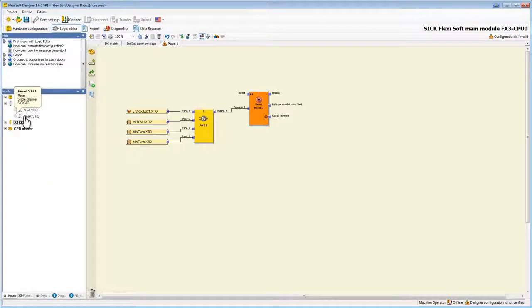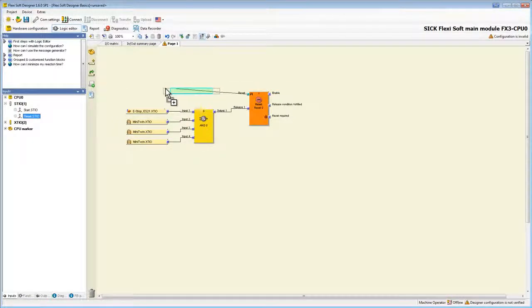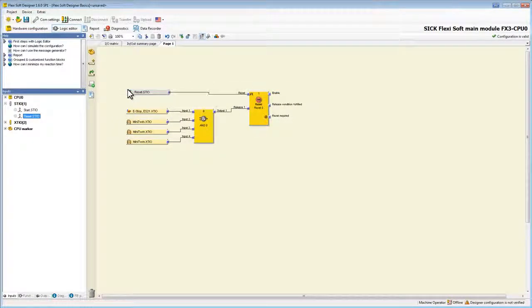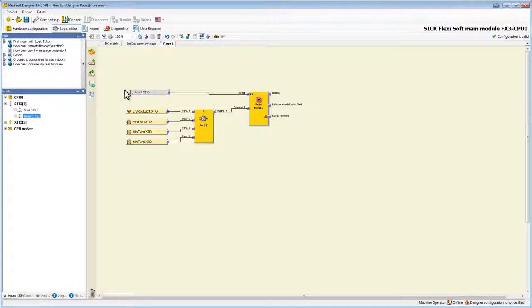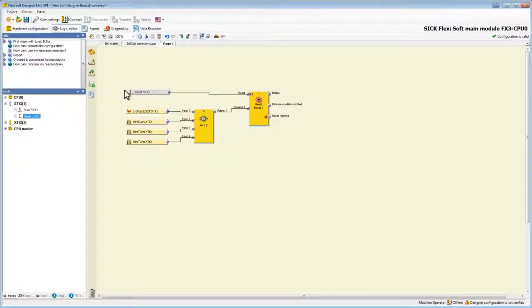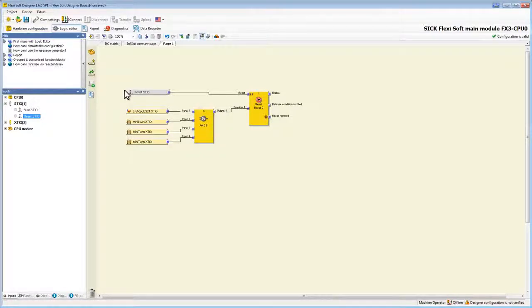Instead of wiring it we can also drag it over the node of the function block and it is wired automatically. In this example we configured the reset as a non-safe element. Therefore it appears gray while the e-stop and the light curtains as safe elements are yellow. This makes it quite easy to distinguish between safe and non-safe elements.